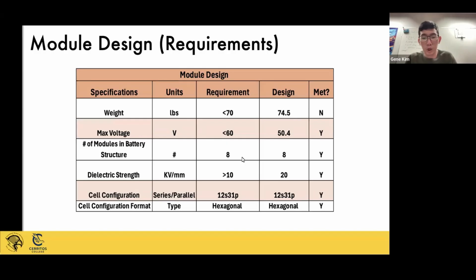Here we compare our module's design specifications to the required targets. We evaluated factors such as weight, maximum voltage, module count, dielectric strengths, and the cell configuration. As you can see, the design meets all requirements except weight, coming in slightly above the 70-pound limit at 74.5 pounds. However, all other specifications, including voltage, structural layout, and electrical safety requirements were successfully achieved, confirming that the module design is largely compliant with our original design targets.